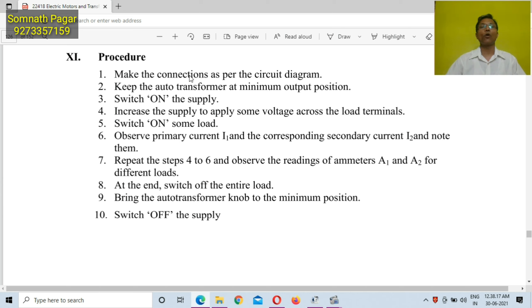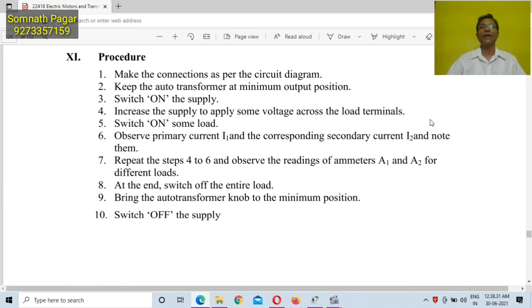This procedure you will follow while performing the practical: make the connections as per the circuit diagram. Keep the autotransformer at minimum output position. Switch on the supply. Increase the supply to apply some voltage across the load terminals and switch on some load. Observe primary current I1 and the corresponding secondary current I2, and note down the readings.